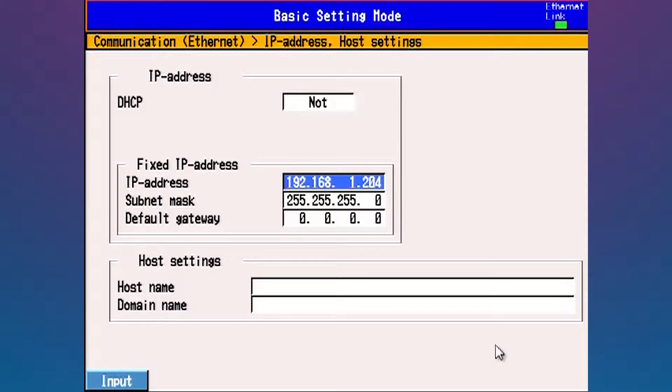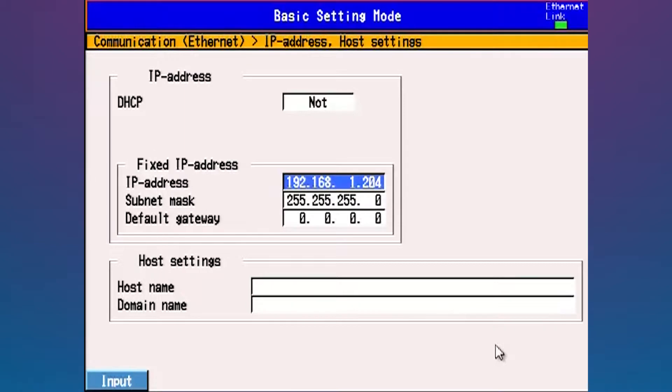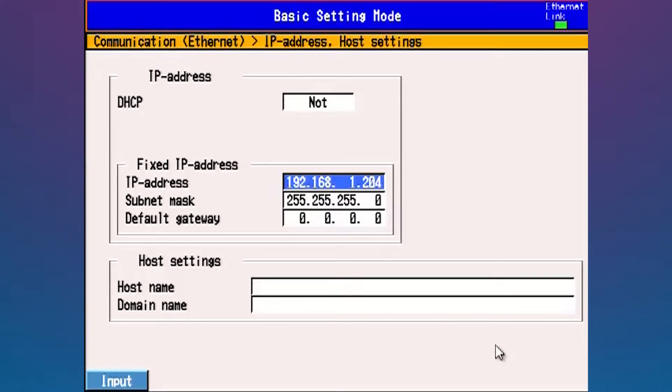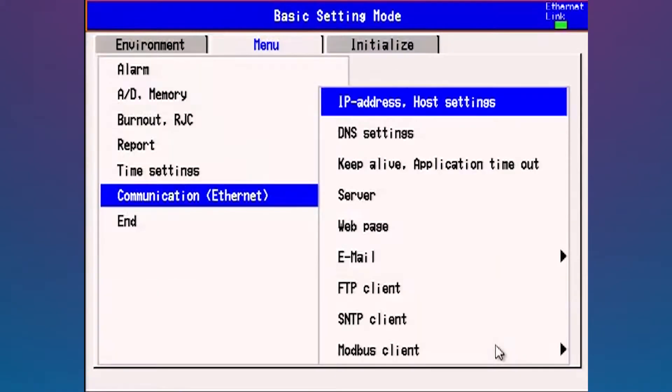To set these, you're going to hit the key below the input in the bottom left corner, and that allows you to go in there and set the numbers. If you don't really know too much about IP addresses, you might want to talk to your IT administrator to get him to assign you some. One thing I'll say is whenever you're configuring stuff, if you see the background in yellow, that means the change is there but it's not committed to memory. To commit stuff to memory, hit your display enter key again.